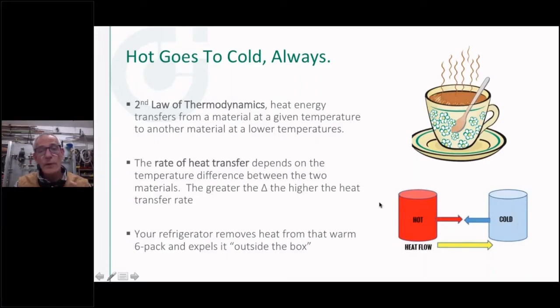So when we look at moving heat, we look at running at different delta T's. And if we can run at a wide delta T, we can move a lot of heat. And I'll give you some examples of types of systems that we run at wide delta T's or narrow delta T's. Why would you choose one or the other? What's the pros and cons of that? So same thing here. We look at heat. We can transfer heat 3 different ways, and we do in hydronic systems. We can do conduction, where if I put my hands around that coffee cup, I would feel the temperature coming out of the ceramic or whatever that cup is made out of.